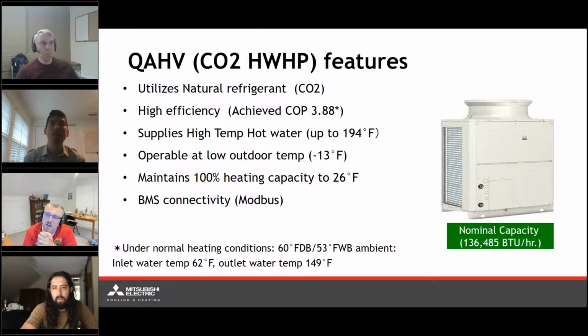That's a great question. For this, I have limited information about the derates, but I'll go with the anecdote that we always talk about within Mitsubishi in its current installations in Europe. There is one particular install that's in northern Scandinavia. My Scandinavian geography escapes me. I believe it's Norway, but regardless, it's a place that gets really, really cold. And at this particular installation, when it was below minus 20 degrees outside, just to test, they wanted to see how much hot water at what temperature they possibly could get. And they were still able to get scalding hot temperatures in their showers, even below minus 20 degrees.